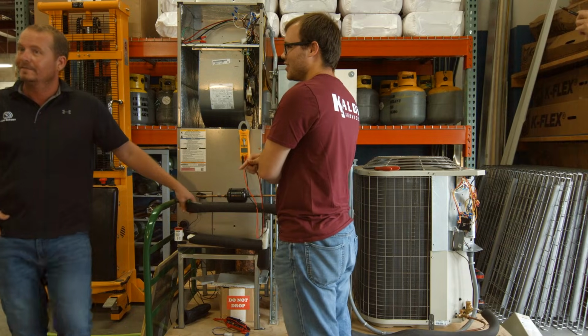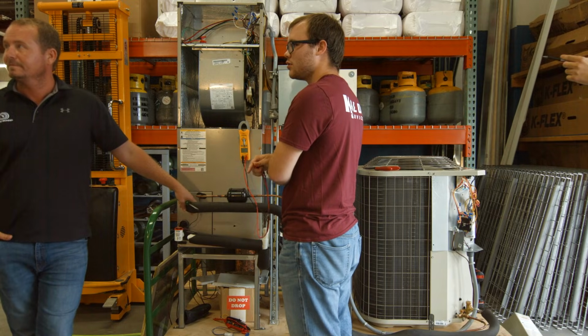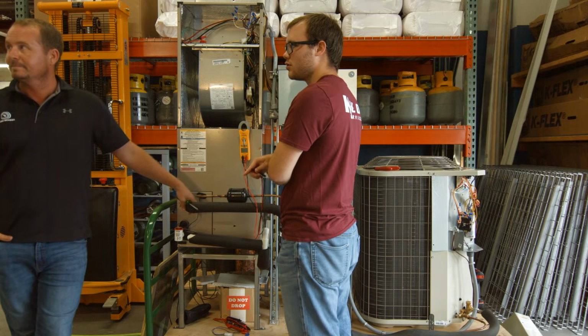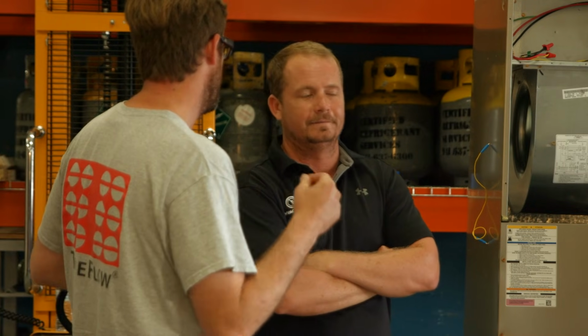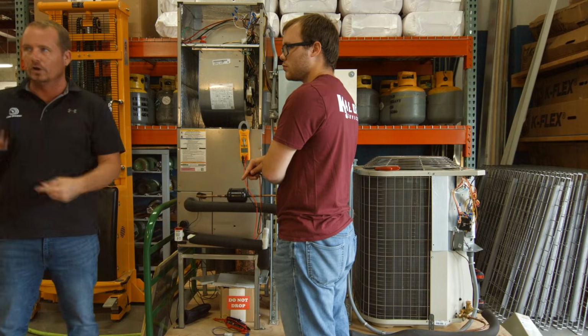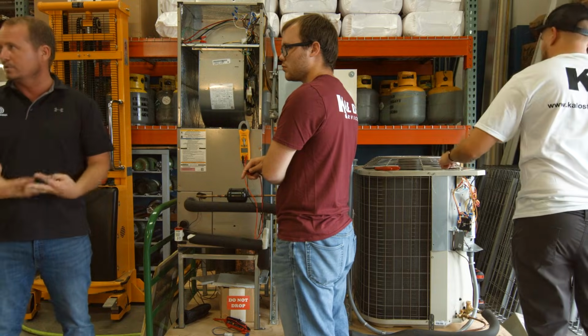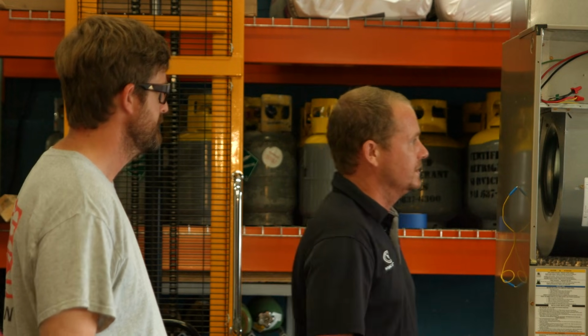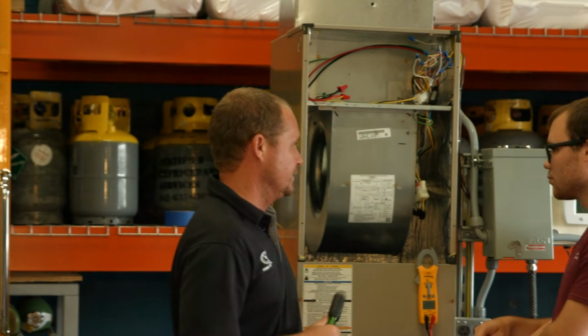We did an install and we reused the line set and low voltage. That's what they wanted to do. And we had different colors outside than inside, and only some of the conductors were spliced. It was a straight cool before with a furnace, so we went to a heat pump, so we needed more conductors. Luckily, we found some that worked. Anytime you are splicing wires, you splice all the conductors. If you've got 8 conductors, you splice all of them. That's the first thing that Dave Barefoot taught me. Actually, I don't know if it was the first thing, but it's something he taught me.